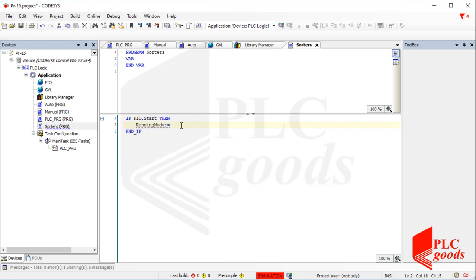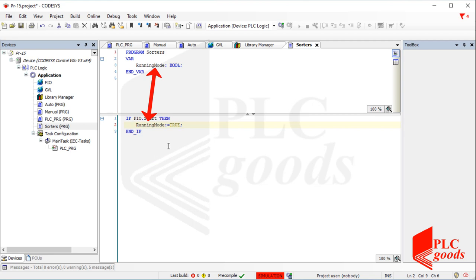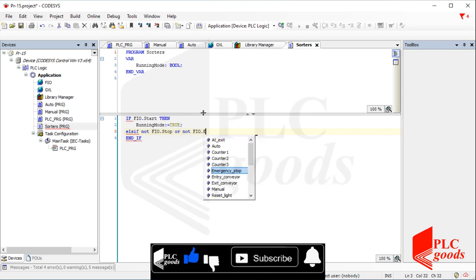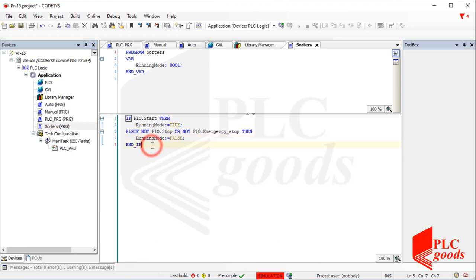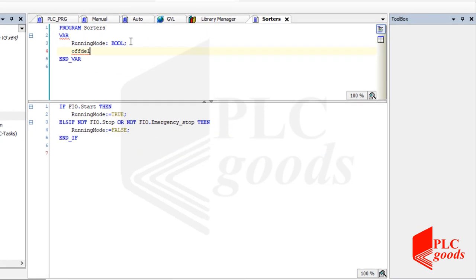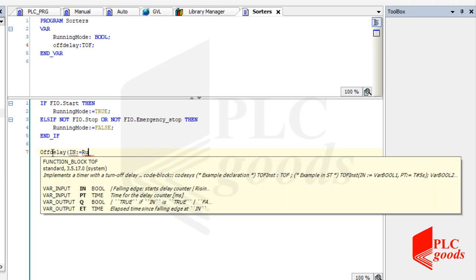I'm defining the running mode variable. Note that it's a local variable inside the current POU, and its full name is different from the previous one which was defined as a global variable inside the GVL list. Also, I need an off-delay timer, because the three arms must remain on for 15 seconds when the running mode variable is disabled.